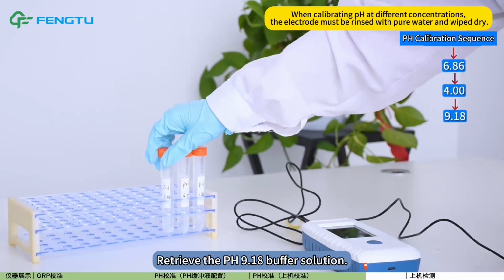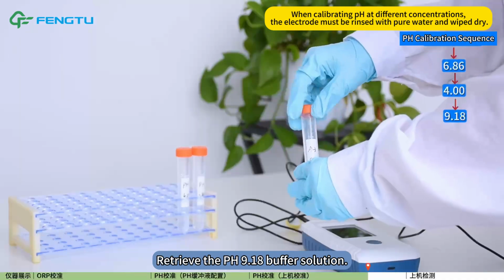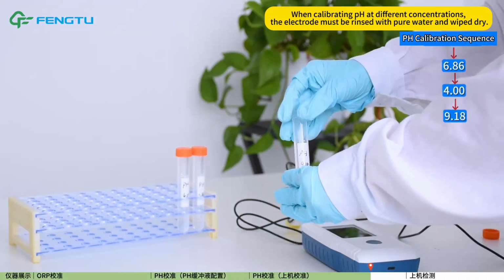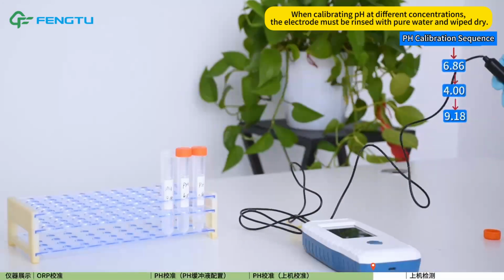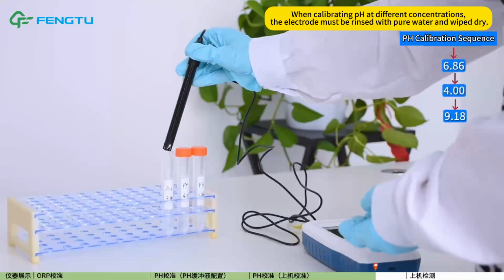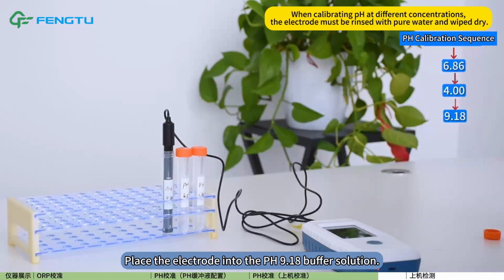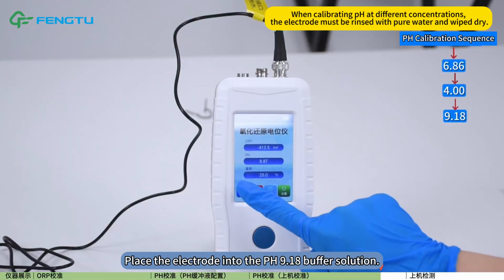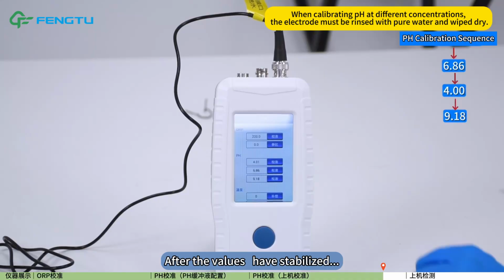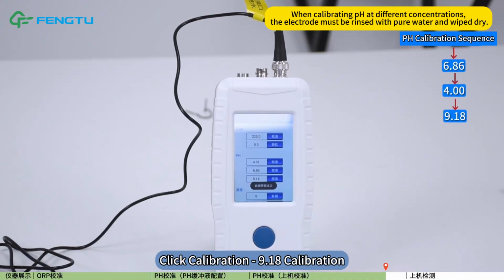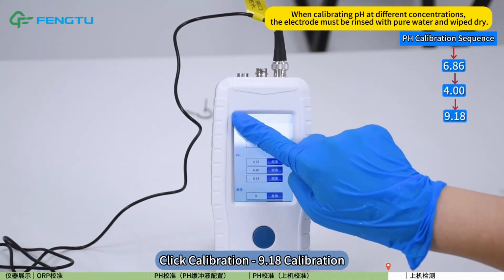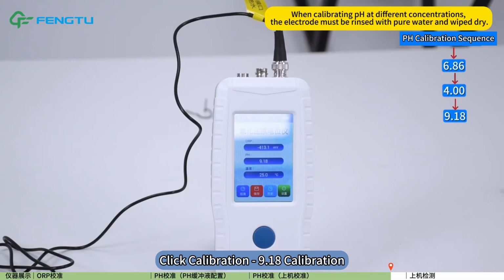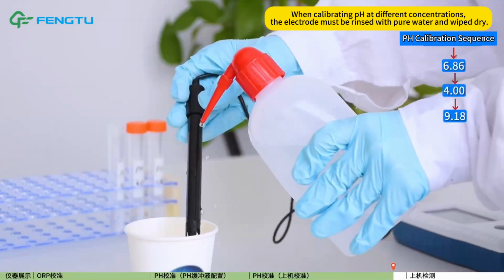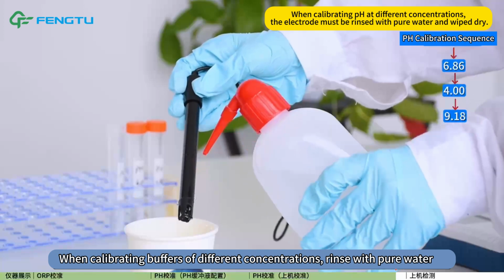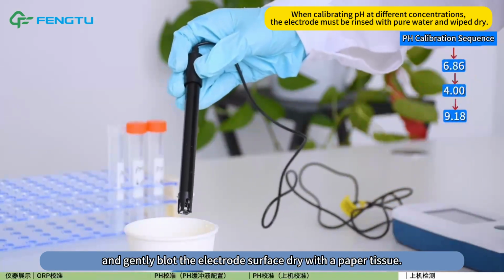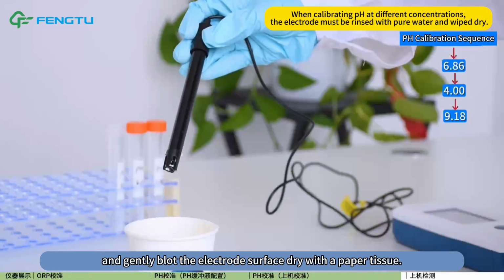Retrieve the pH 9.18 buffer solution. Place the electrode into the pH 9.18 buffer solution. After the values have stabilized, click Calibration 9.18 Calibration. When calibrating buffers of different concentrations, rinse with pure water, and gently blot the electrode surface dry with a paper tissue.